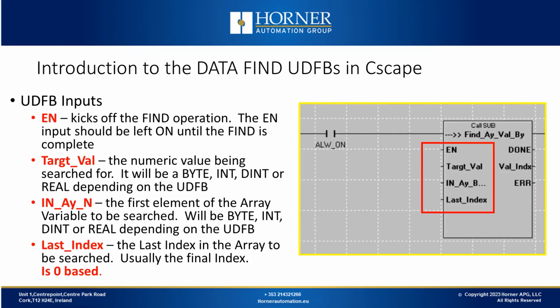Now we'll look at the specifics of the data-find UDFBs. Every user-defined function block has inputs and outputs, and that's true of the function blocks that are built into Cscape as well. So we'll look at those 4 inputs for the data-find UDFBs. Firstly, the enable input, which is labelled as EN, is used when it is turned on to start off the find operation. So turn on enable and leave it on until the function block is done with its job.